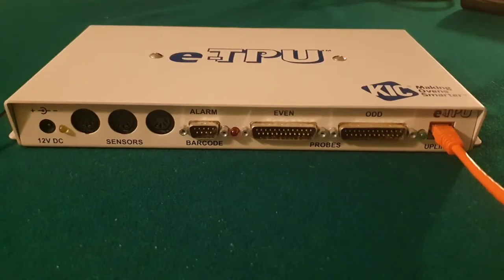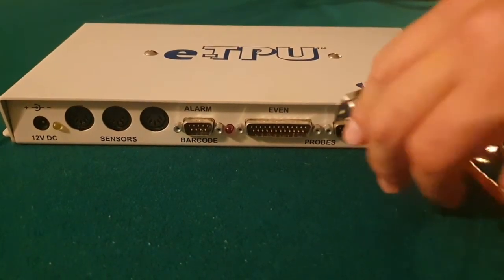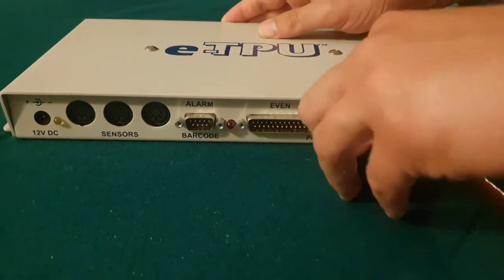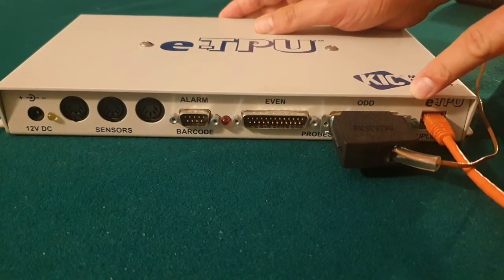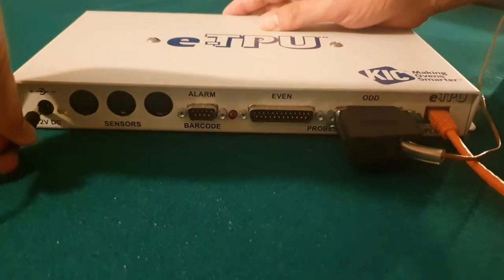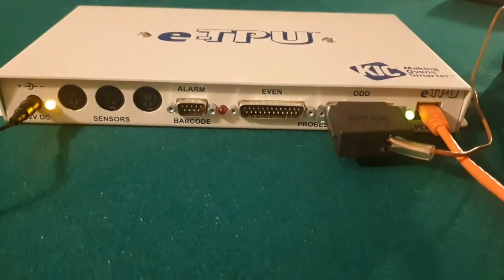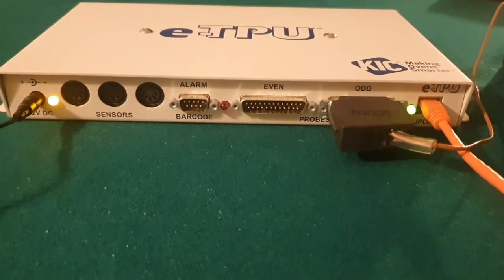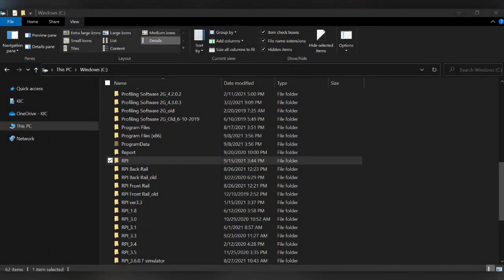In the calibrator, you may have two channels. One channel may be an input to read or measure thermocouple temperature. The other should be an output to be used for simulating a K-type thermocouple output temperature for calibration. Please connect the adapter to the calibrator output as shown here. Next, connect the adapter to the odd port in the eTPU. The eTPU is now powered and connected to the calibrator.